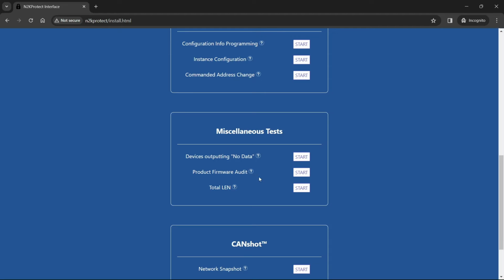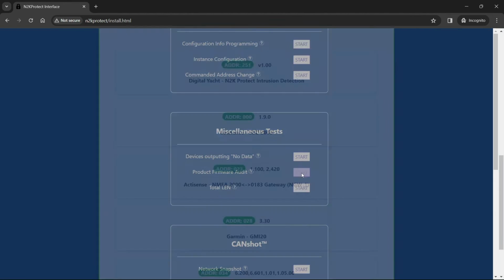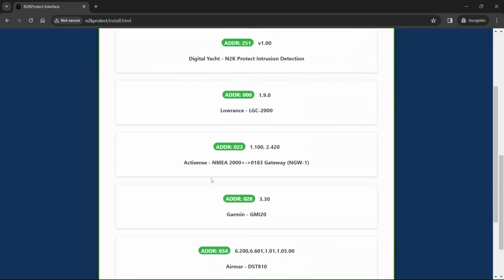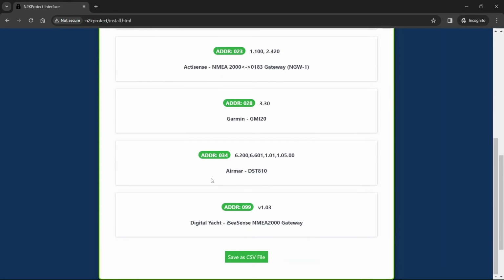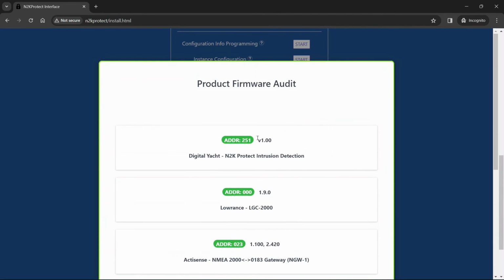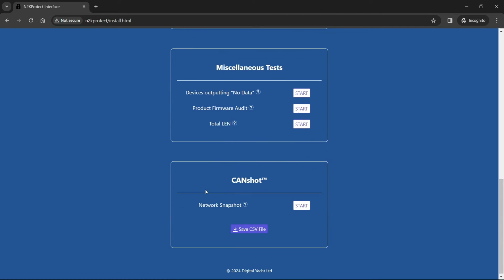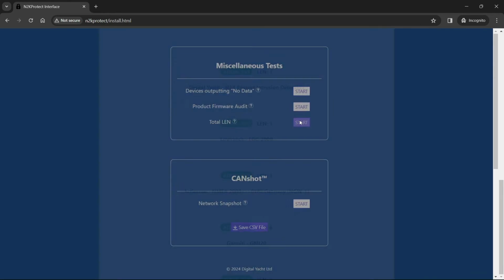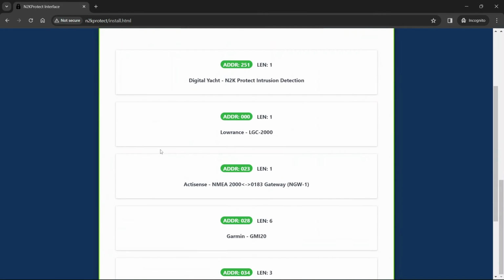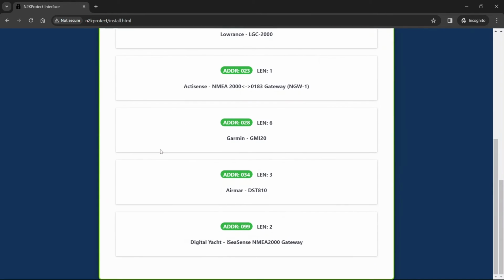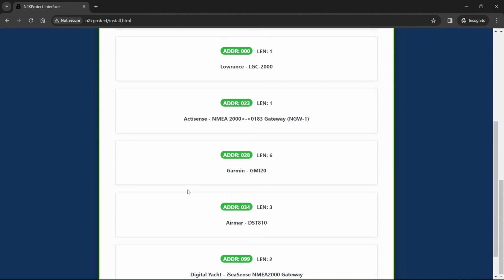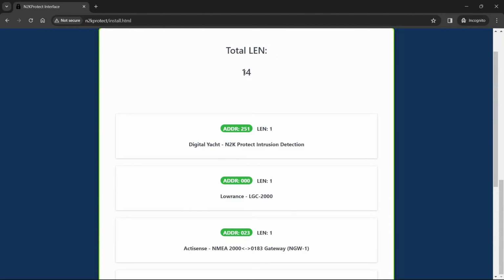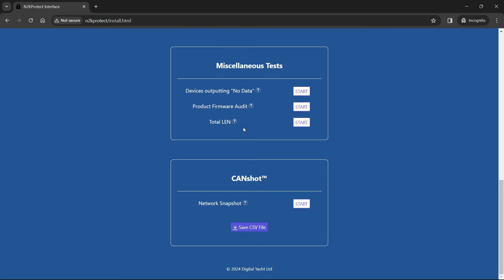We can also do a product firmware audit, where it will list all the devices on the network with all the versions of firmware inside, and you can save that as a CSV file, which is useful for the installer. Last but not least, you have the total LEN calculation - another important one. It calculates the power that each of the devices is taking and works out the total for you, so you can make sure all the cabling is capable of taking that amount of power.